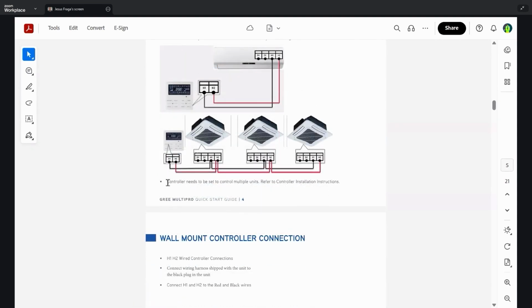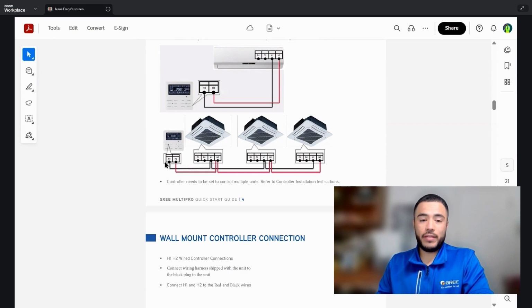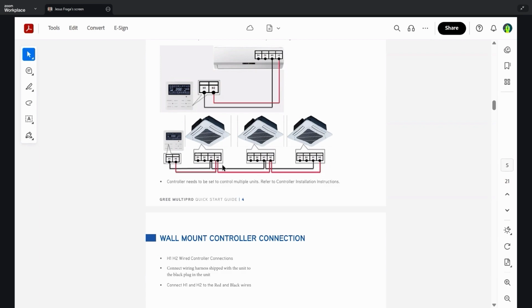Another key feature here is if you wanted to control multiple units using one wired controller, you can do this by daisy chaining the thermostat terminal block H1 and H2 from indoor unit to indoor unit to indoor unit. Depending on how many indoor units you want this wired controller to control is how long your daisy chain will be. Please remember that the wired controllers are only capable of controlling up to 16 indoor units via one controller. So just keep that in mind.